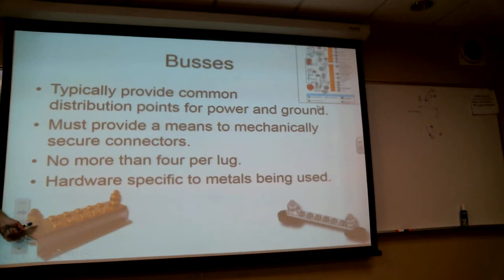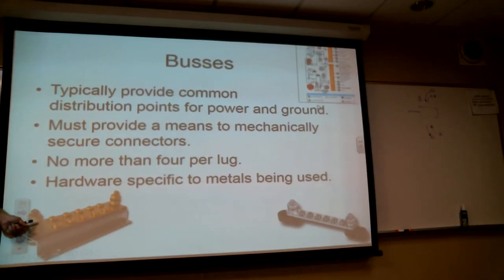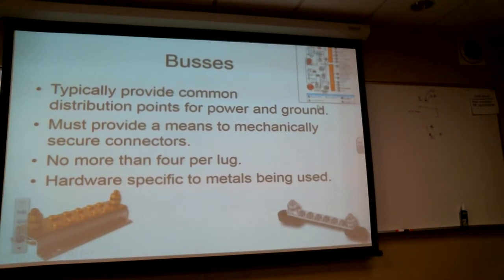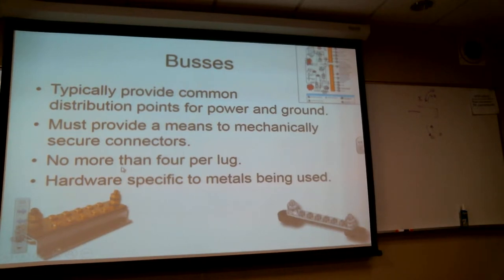There are a variety of different strategies. You'll go to the appropriate document to find out the correct washers, lock washers, and types of metals. Typically — although I've seen this violated by manufacturers — you don't want more than four connections per lug. It's a redundancy thing, reducing the number of things that get taken offline if a screw comes loose.